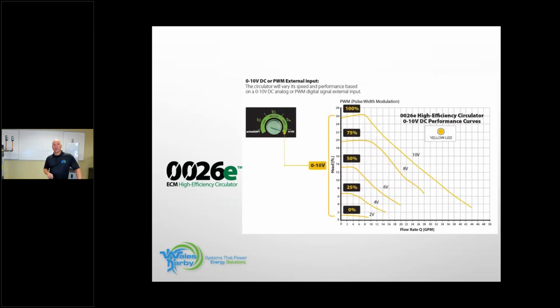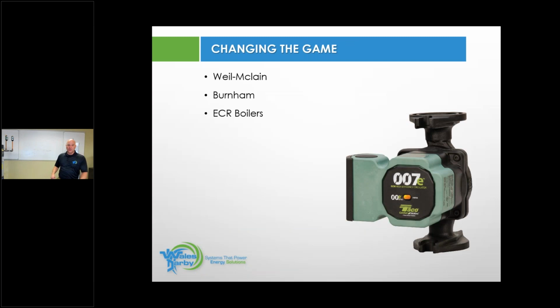And this right here just shows you what I talked about earlier with an ECM circulator. Here at 100%, that's 10 volts, and it works its way all the way down to 2 volts and 4 volts and so on down the line. That's what's going to change automatically on an ECM circulator as it's running in comparison to an AC-driven circulator. So just so you have a heads up going into this as to what you're looking at.